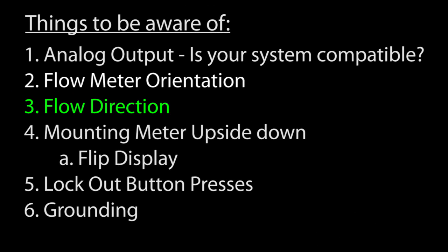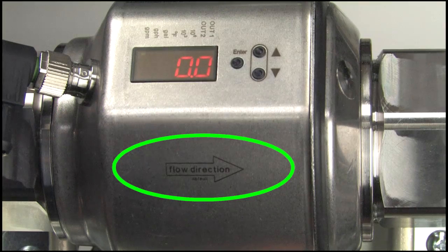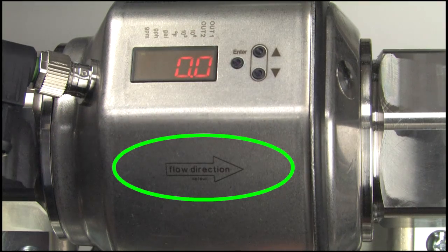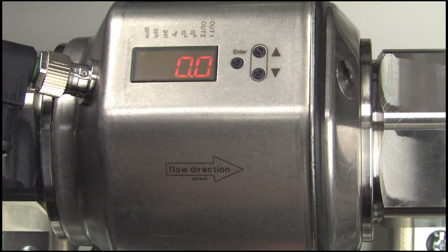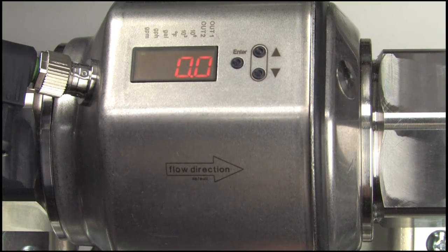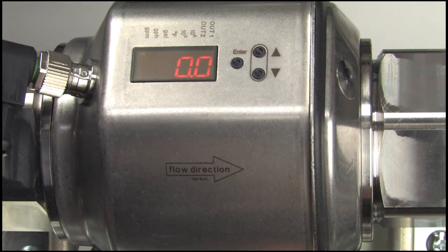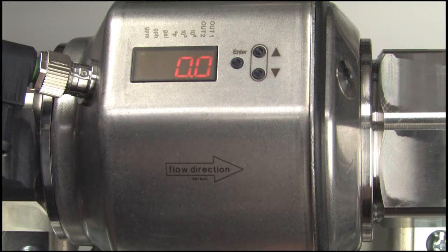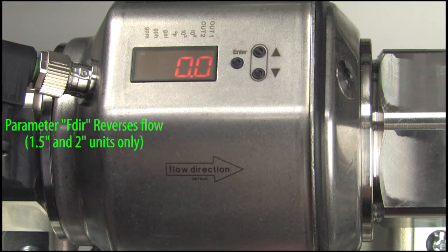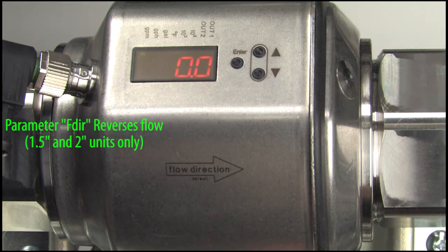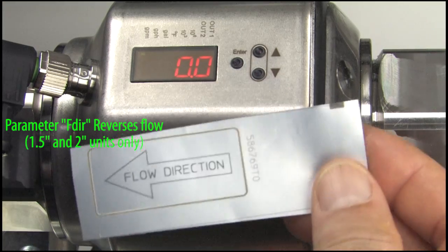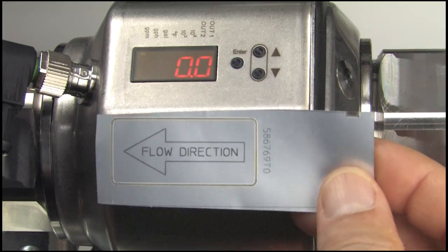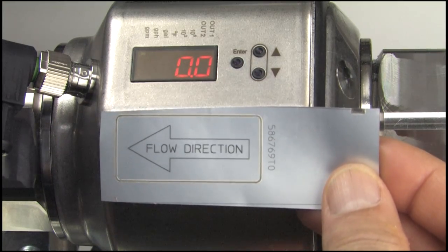Flow direction is very important. There is an arrow etched on the side of the unit. The display will show negative flow if you get it backwards but the outputs won't do what you expect. On these 1.5 inch and 2 inch units, you can reverse the flow in a menu setting and they even come with a little arrow sticker you can put over the etched arrow on the housing.